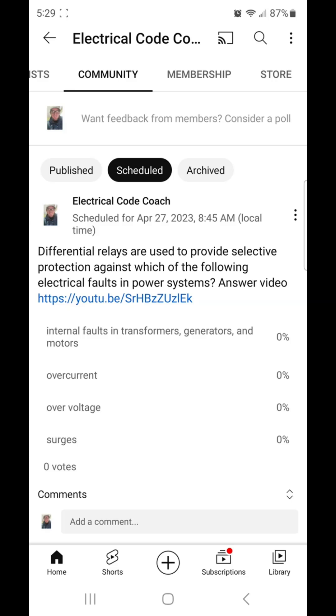We are going to isolate a part of the circuit or part of the system. Let's say we isolate one motor. Set a motor in the center — before the motor we start the zone, and after the motor we start the zone, and in the middle we put the differential relay. It is going to act essentially like a current counting machine, just like a GFCI does.